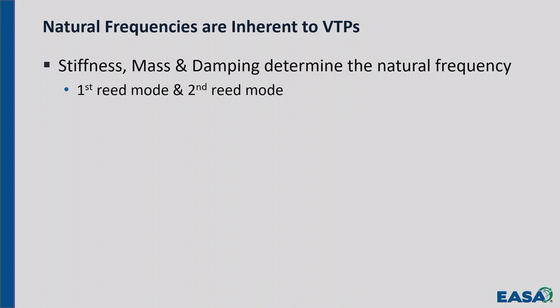You've got another issue here, and that's that the motor sticks up and the pump sticks down. So you've got at least two different potential reed frequencies, one on the motor and one on the pump. When you install a new motor and it's vibrating, and a customer is saying, hey, I can't have that high vibration, it's something you did with the motor, the problem could be that the pump is down there going 10 times as much as the motor is. If you don't have any means of figuring that out, and you chase this vibration problem up on the motor while down below the pump is going 10 times, you're not going to solve the problem until you figure out that it's the pump, not the motor. So, first and second bending modes: you've got the motor, you've got the pump.